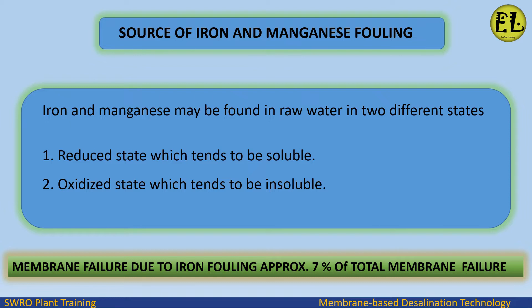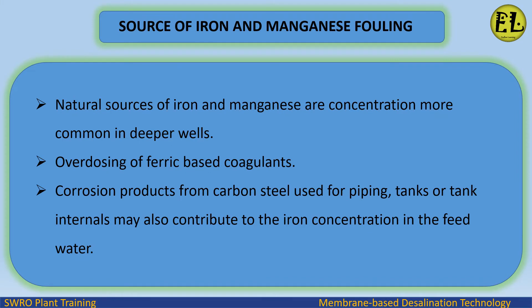Membrane failure due to iron fouling accounts for approximately 7% of total membrane failures. Natural sources of iron and manganese are more common in deeper wells. Overdosing of ferric-based coagulants, as well as corrosion products from carbon steel used for piping, tanks, or tank internals, may also contribute to the iron concentration in the feed water.